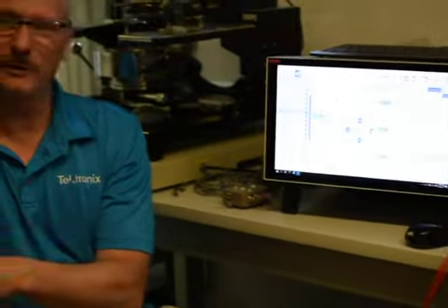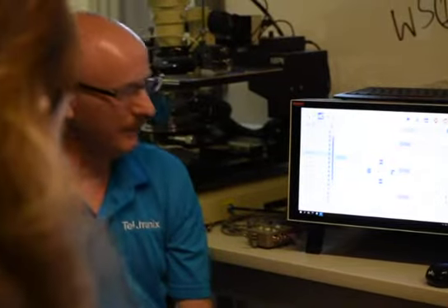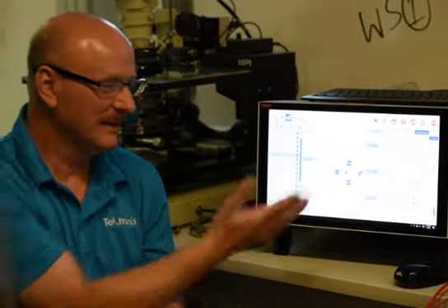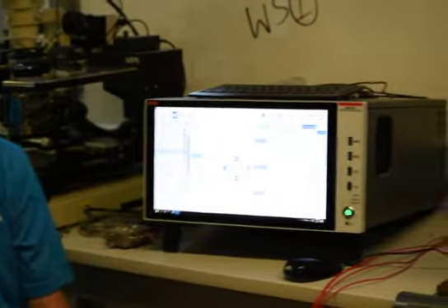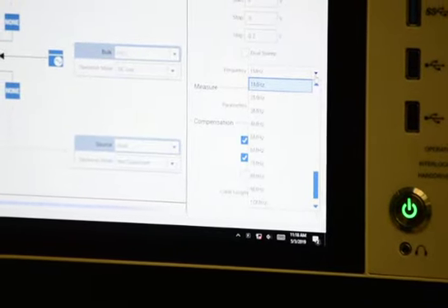Some customers are asking for 2 volt AC drives. They want to measure really small currents. And another thing that we're looking into is the frequency. We give you set frequencies. You can't measure at 1.5 megahertz, for instance. We're wondering if that's okay. We want to hear from our customers. Is this something you'd like to see? Would you like to see more resolution on this, or is that okay? We're trying to get some feedback to see if we need to modify any of this stuff.